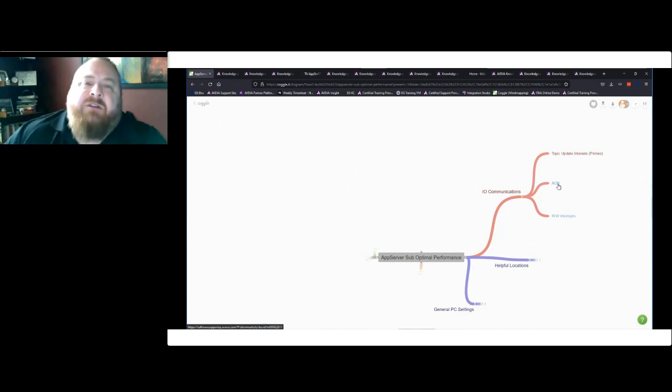And so Advanced Communication Management allowed us to control on a per topic basis if we wanted to advise only active items. And active items are things that are used in a script, historized, alarmed, used in an animation. I might be forgetting one more there, but anyway. It acts more like the advise only active items and less like the advise all items, so thereby decreasing the load on your network. Now, I have seen this cause problems. I have seen this fix problems.